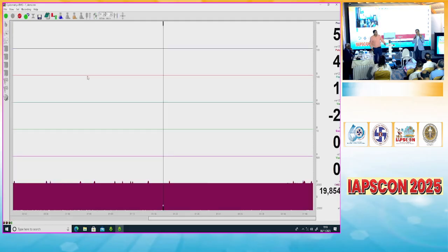EMG gets damaged often, it is a very sensitive instrument, and you have to replace it, or either you have to have an AMC with the company and all that. One technical tip to make its life longer is to charge it before every case, not just keep it charged forever. We don't do EMG in most of our cases. In 50% of our cases, we do not do EMG. Only if I tell her a day before that tomorrow EMG will be done, she charges it 15 minutes before the study. There's a battery which needs to be charged. If you don't keep it in a charged state, the life is better, but it is very costly. So it's not mandatory.